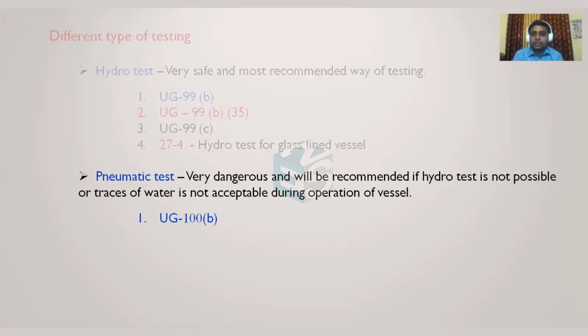Pneumatic testing is preferred when hydro testing is not possible, when liquid traces after the test could create operational problems, or when the vessel geometry or support arrangement cannot withstand the weight of the water that would fill the vessel during hydro testing.